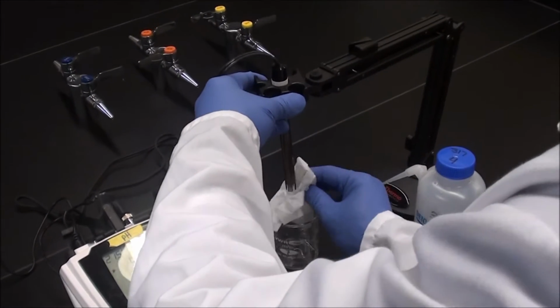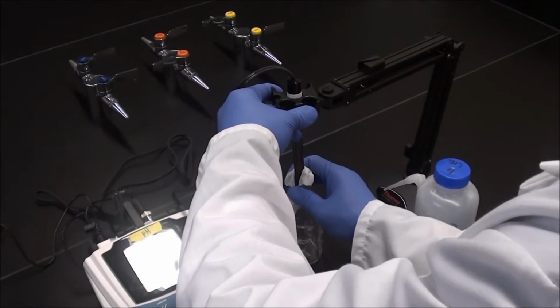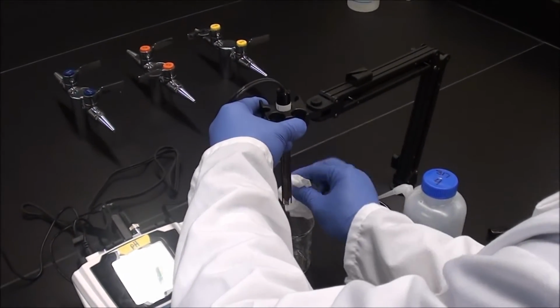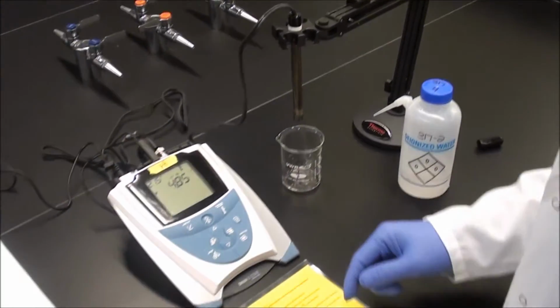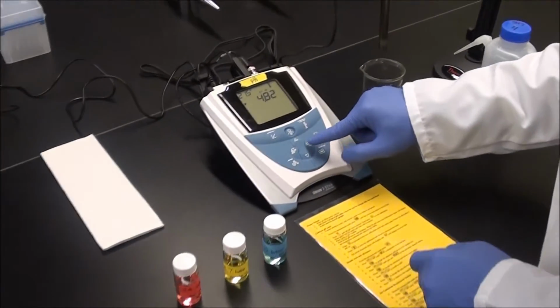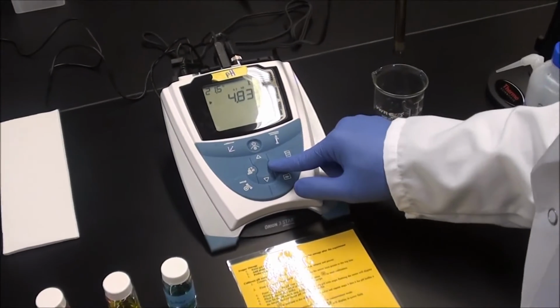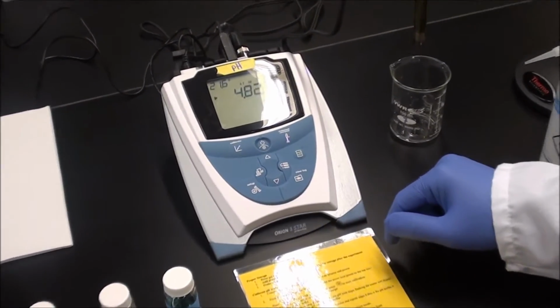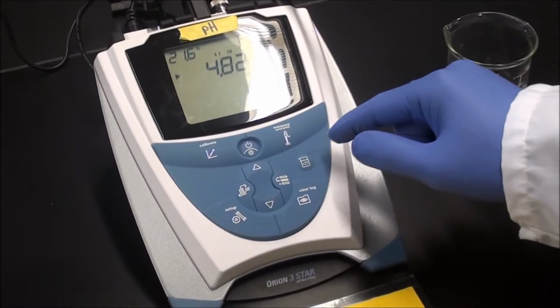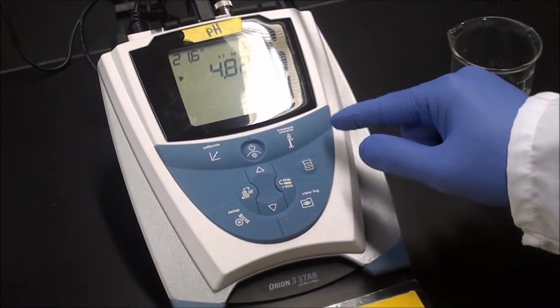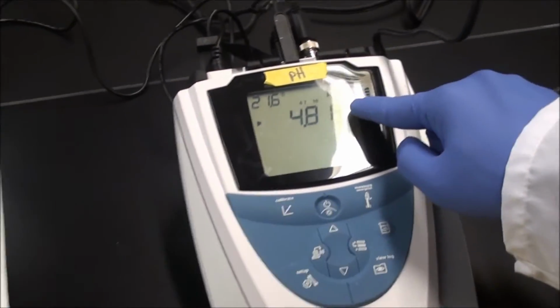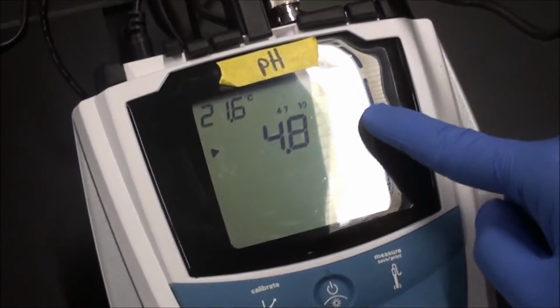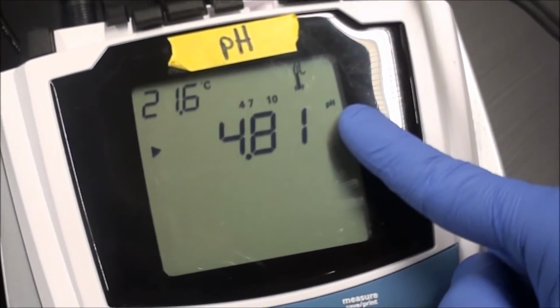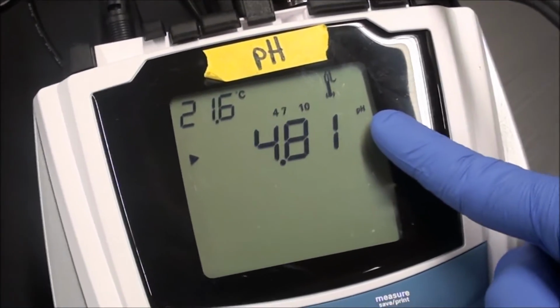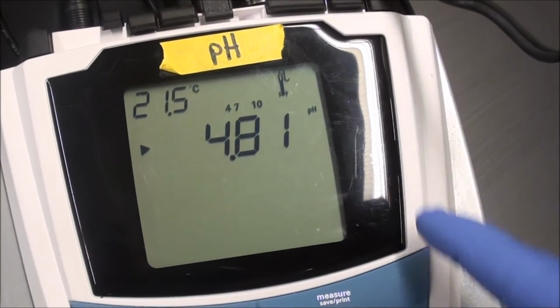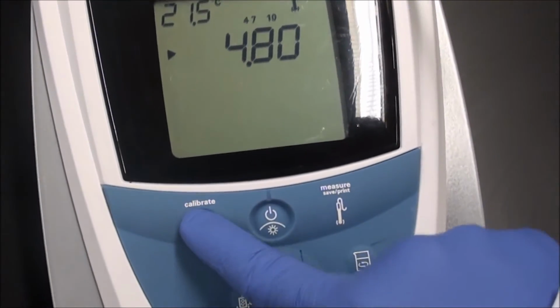And then once everything is connected to the adapter and the power, from the measurement mode, press this little button right here to start the calibration process. And as soon as you press that, the icon at the top will be showing. And if it says pH on it, you want to go ahead and press the calibrate button.